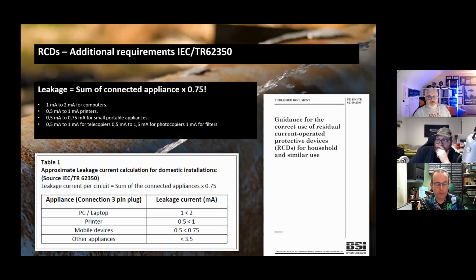So we need to accept that the split load RCD board is definitely coming, which in theory for a lot of electricians should be a stimulator. It's going to be interesting to see how people are coding this, but I agree this could be worded better. It should be worded better, and there should be guidance. And I'm going to make the comment when I do my commenting. There should be an appendix that gives all of the leakage, so that electricians can select and erect and ask questions about the use, so that they can take all reasonable steps to design accordingly. Yeah, we don't need the whole lot of the standards, because most of it is about how appliances are made and what criteria they're designed to. So it is literally just a line in each one, which needs to go into a table and be stuck in the back. So yeah, it's a bit of a coding headache. Neil's right. Richard Harrison, bang on.